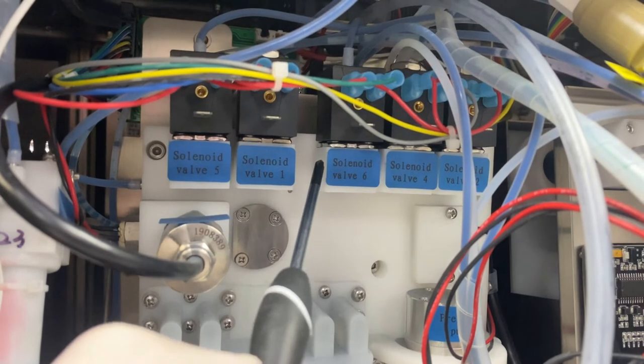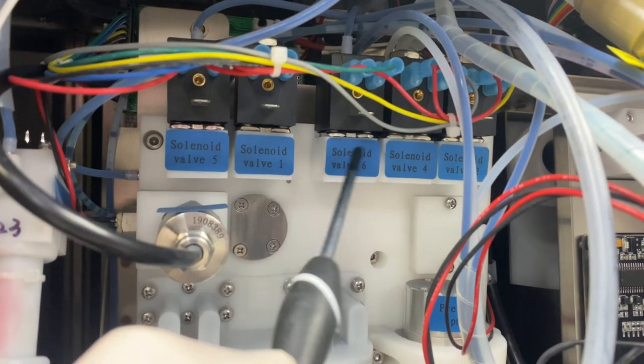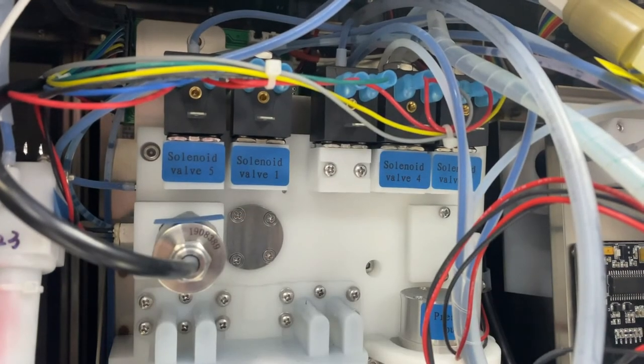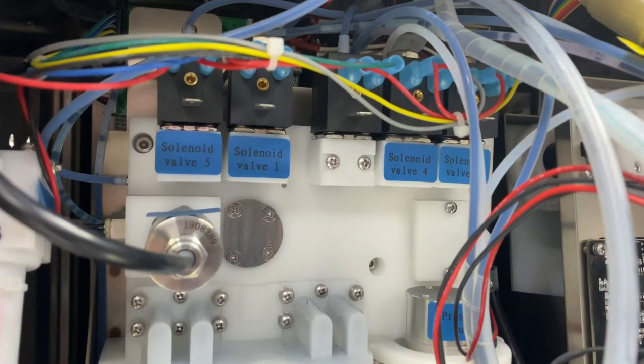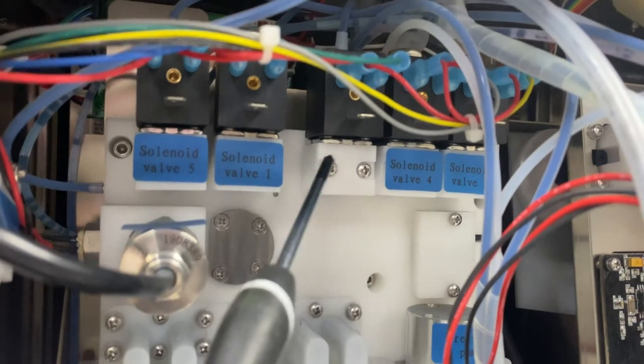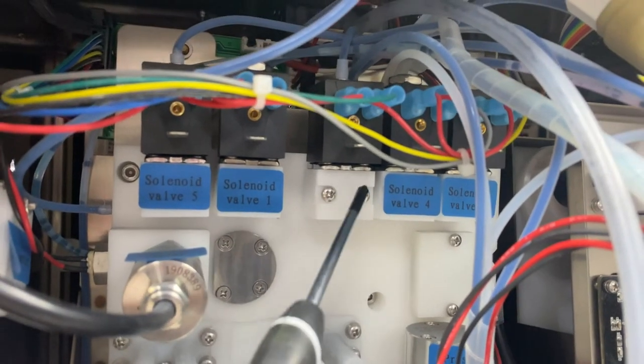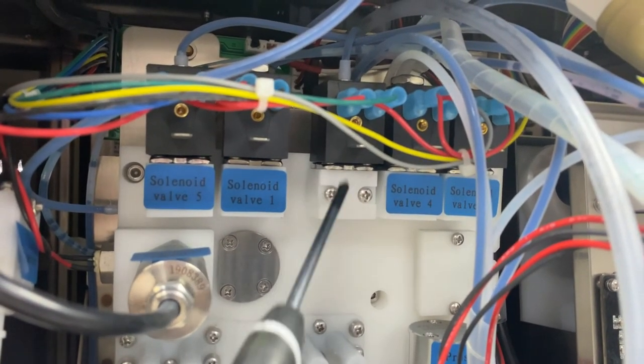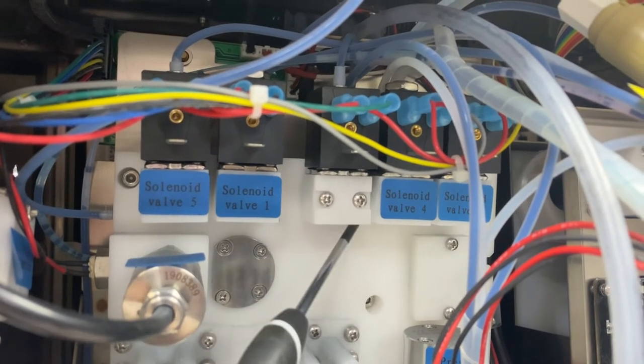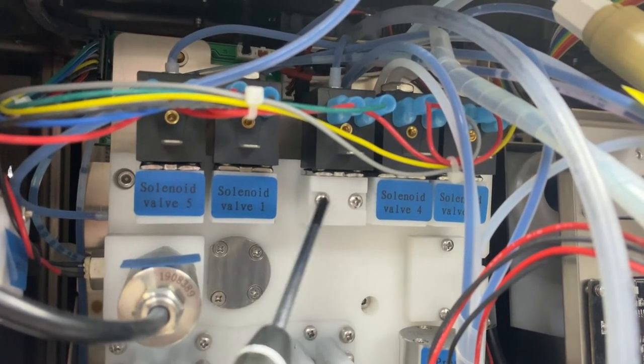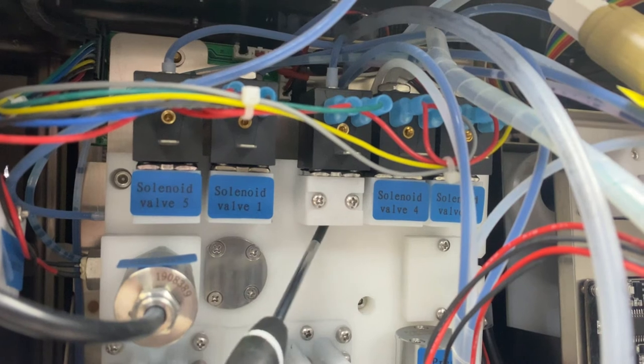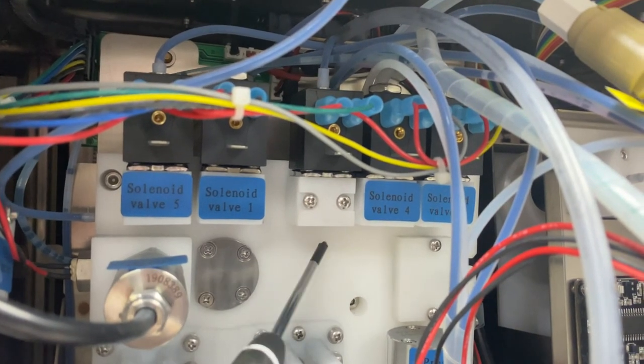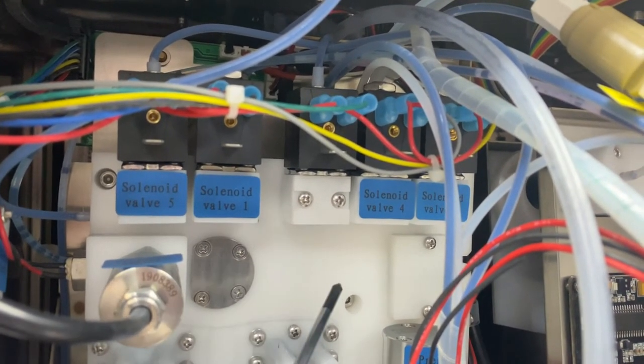First thing we're gonna do is get this sticker out of the way, because the two screws that bolt this to the manifold are underneath it. We're going to take these screws out, which will completely unbolt the valve from the manifold. Being that this is an ink valve, there's always a chance of residual fluid, so be ready with a paper towel or rag to catch that excess fluid.